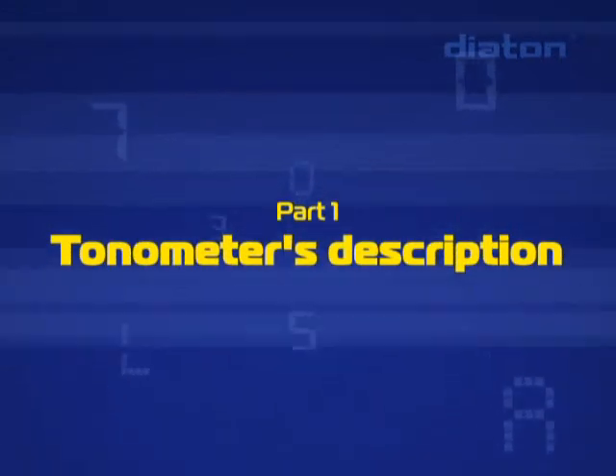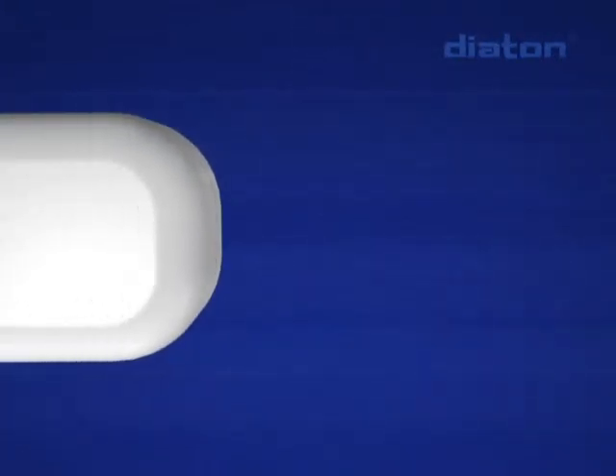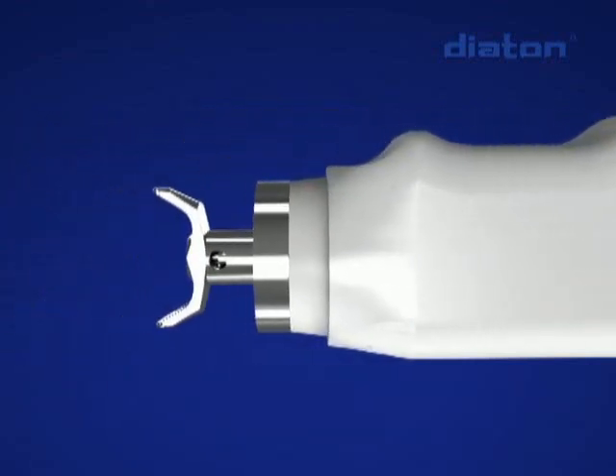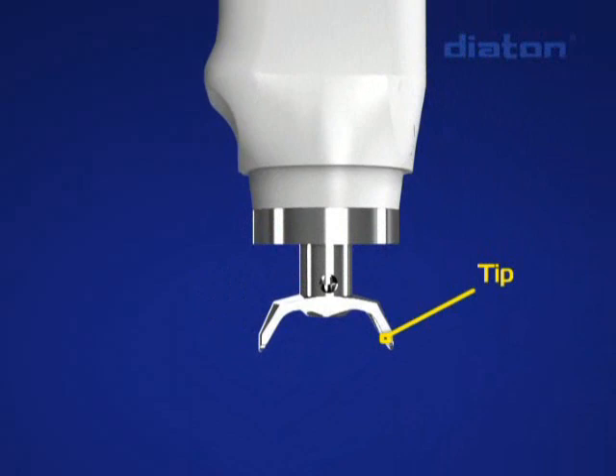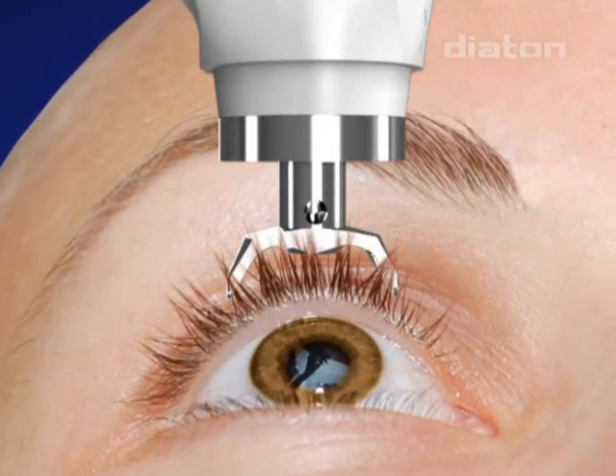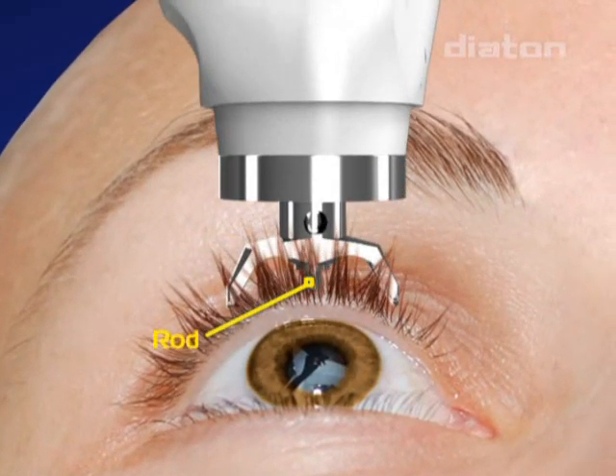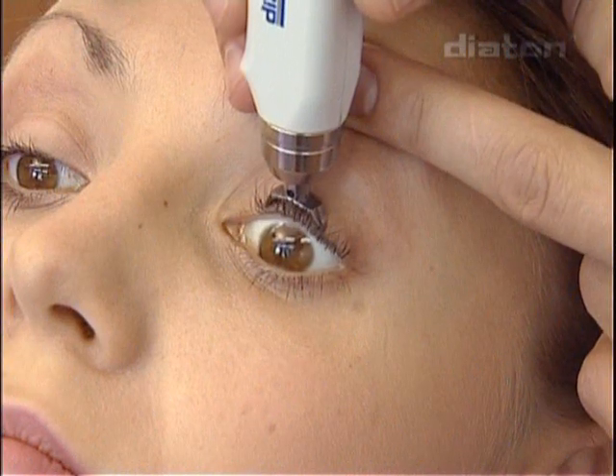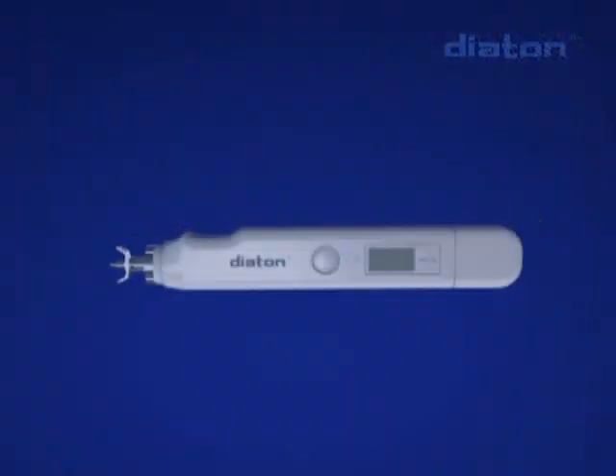The Tonometer has an ergonomic plastic body. The tip is intended to fix the Tonometer at the eyeball on the upper eyelid during intraocular pressure measurement and allow elimination of the damping properties of the eyelid. There is a free-moving rod inside the Tonometer which interacts with the elastic surface of the eyeball via the eyelid in the area of the sclera corresponding to the corona ciliaris.